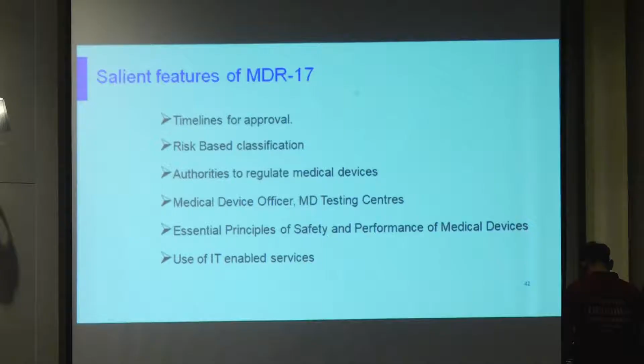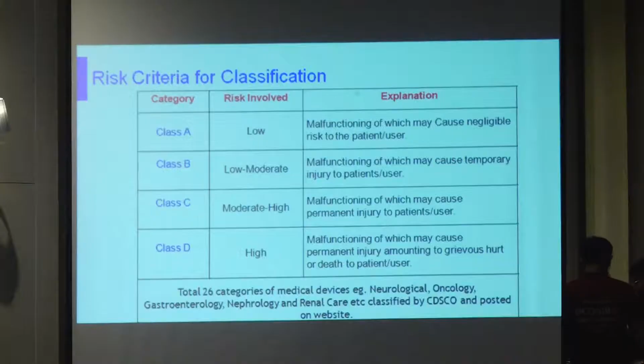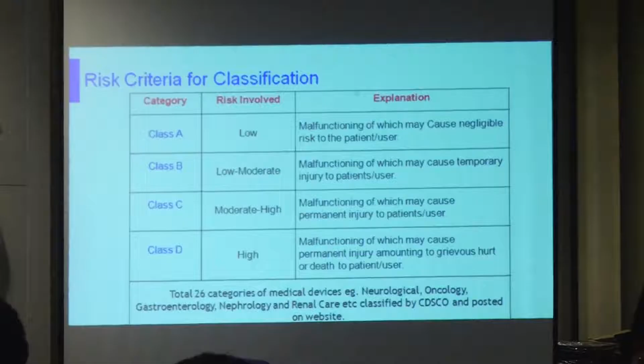I hope if you are able to read and understand this slide, when you say that we have low risk device, high risk device, medium risk device, class A, B, C, D, what is the meaning of a low risk? When you say class A devices, low risk means if any malfunctioning of the device also takes place, malfunctioning of which may cause negligible risk to the patient. This is called low risk device. Low to moderate means malfunctioning of which may cause a temporary injury to patient. Temporary is very important. In case of a moderate to high risk devices, that malfunctioning of which may cause a permanent injury. And finally, high risk device means malfunctioning of which may cause permanent injury amounting to grievous hurt or death to the patient. So that's why while you classify any device, this is mainly the end output of the device what you are approving.